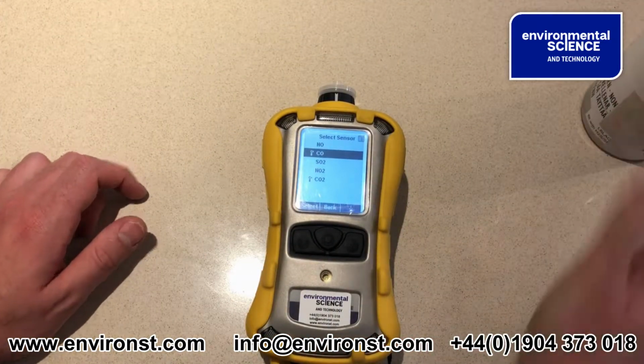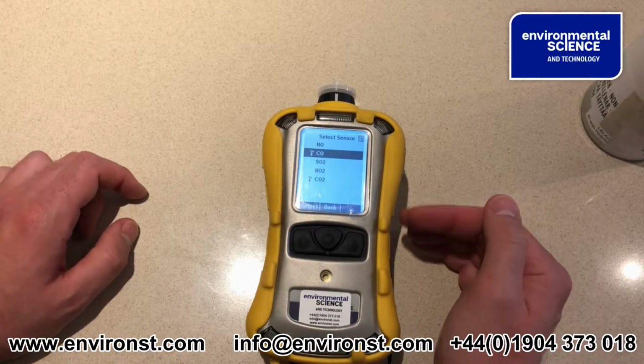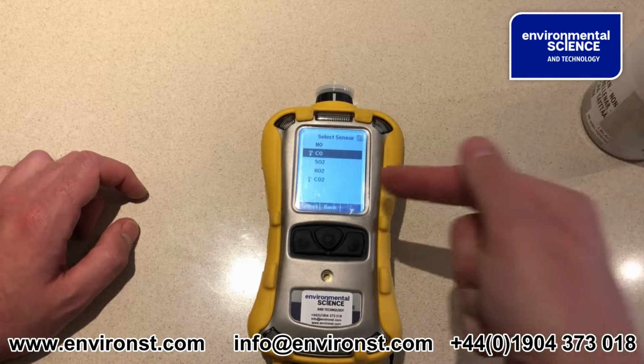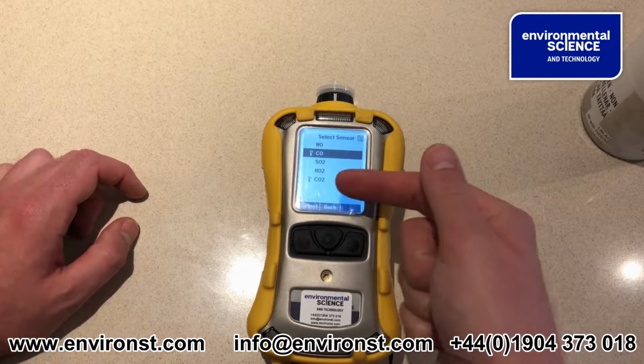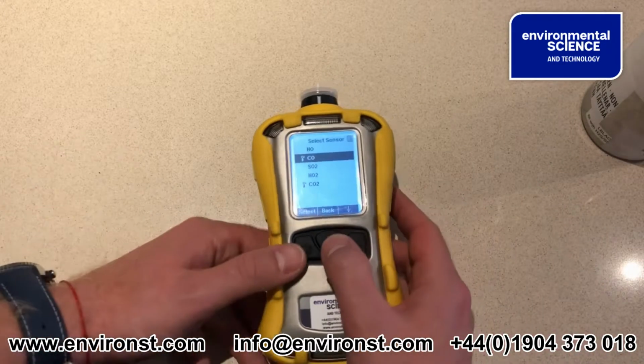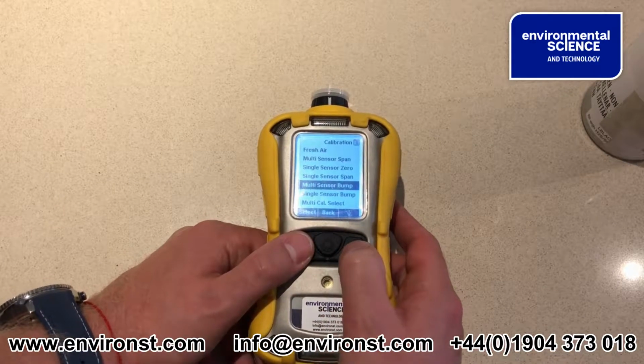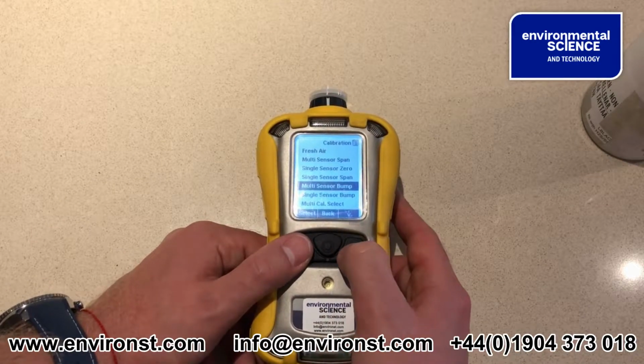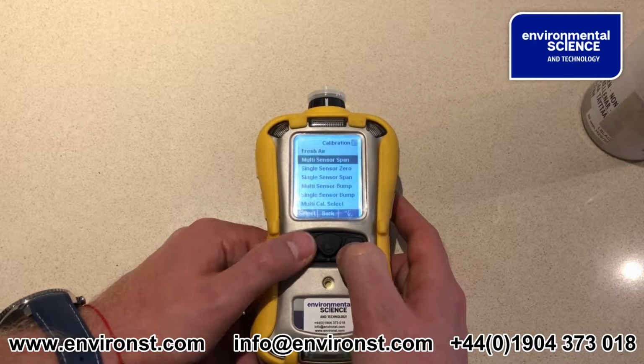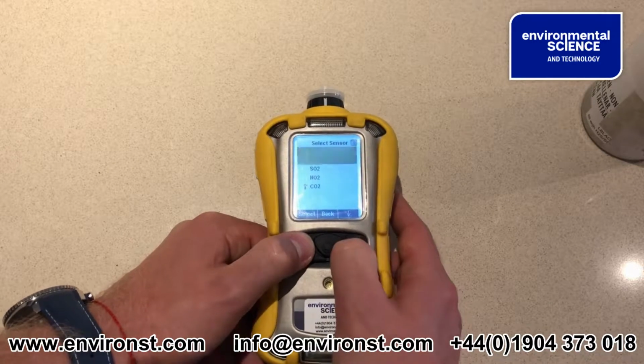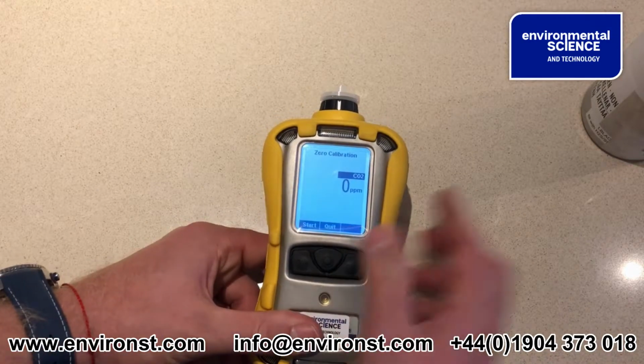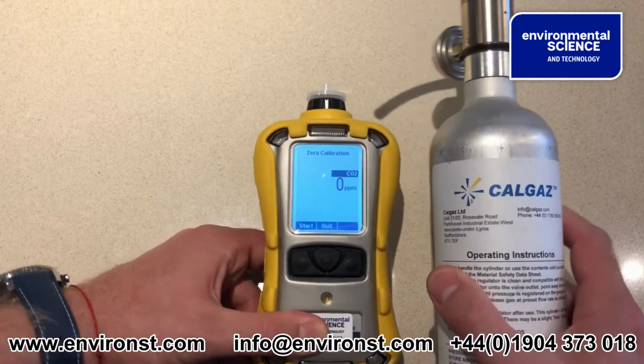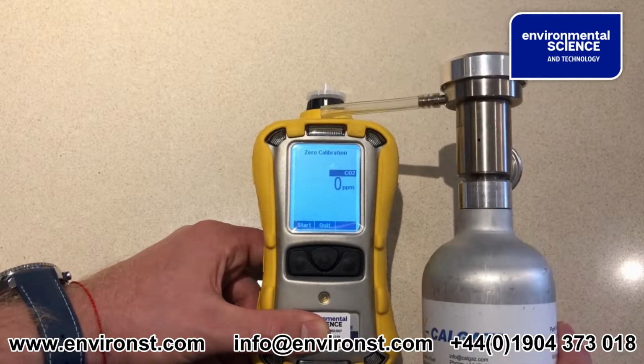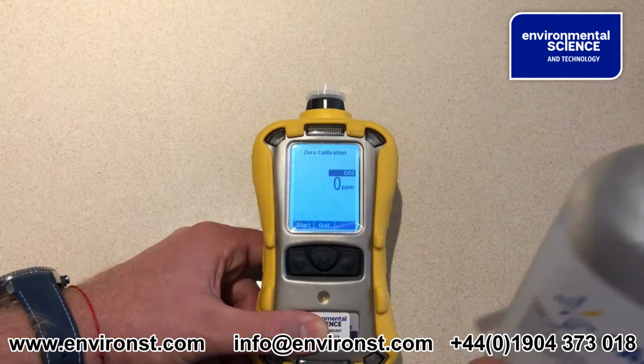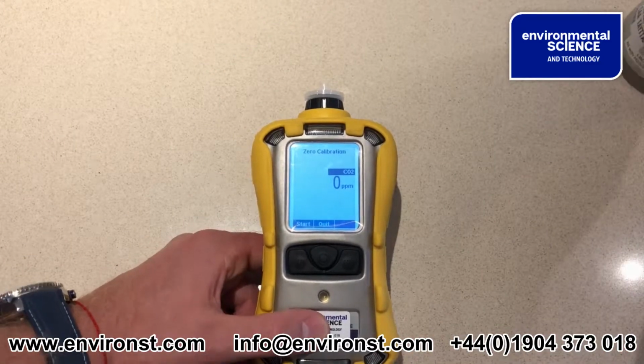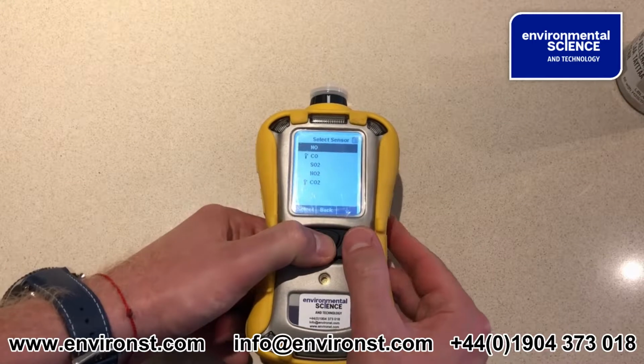And if we wanted to continue calibrating individual sensors, we could then get a different can of gas for carbon monoxide, sulfur dioxide, NO2 and CO2 and carry on doing that. So if I wanted to calibrate a CO2 sensor now, if I were to go around the list and go single sensor span, I went to the CO2, I'd then have to get a canister of pure nitrogen with the on-demand regulator and calibrate it using the same method but with pure nitrogen. So let's quit that menu.